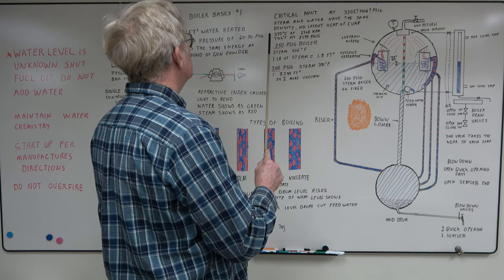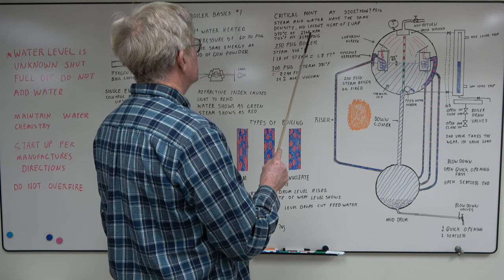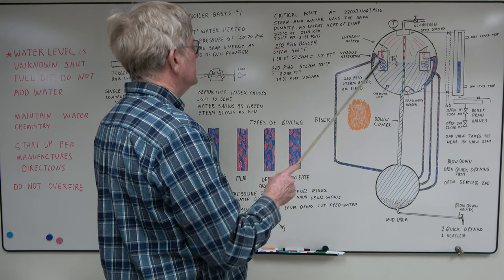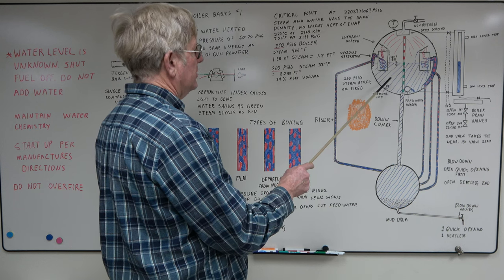In the metric, it'd be 373 degrees Celsius at 22060 kilopascals. A 250 PSI boiler, the steam is at 406 degrees and one pound of steam occupies 1.8 cubic feet.